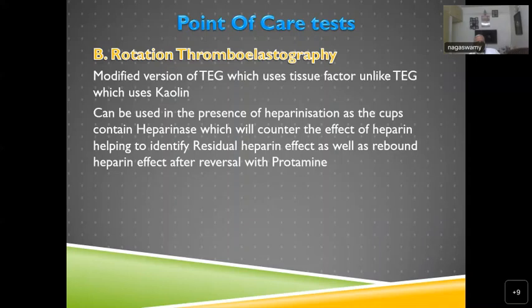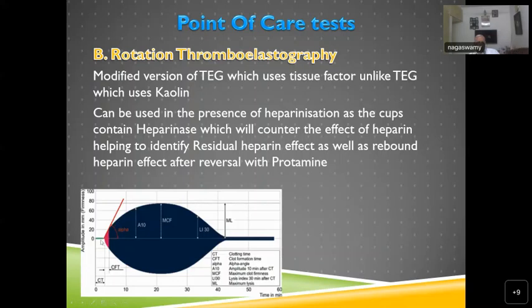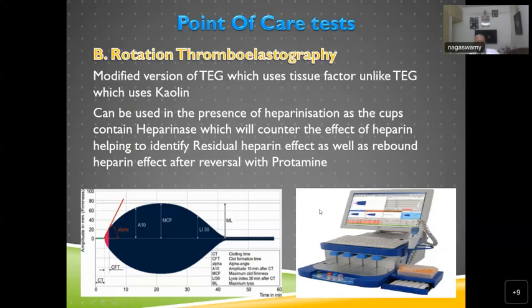ROTEM is a modified version — introduced after TEG. Unlike TEG, ROTEM uses cups containing heparinase, so it can be used in the presence of heparinization, helping to identify residual heparin effect and rebound heparin effect after removal. The graph is similar but terminology differs: clotting time (CT), clot formation time (CFT), alpha angle, and maximum clot firmness (MCF).